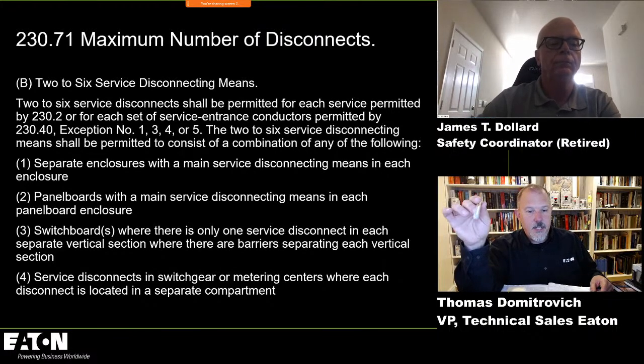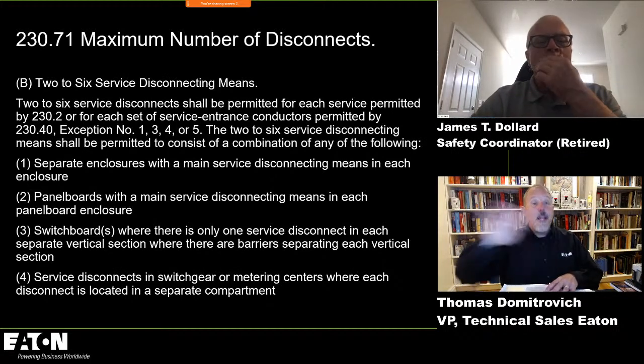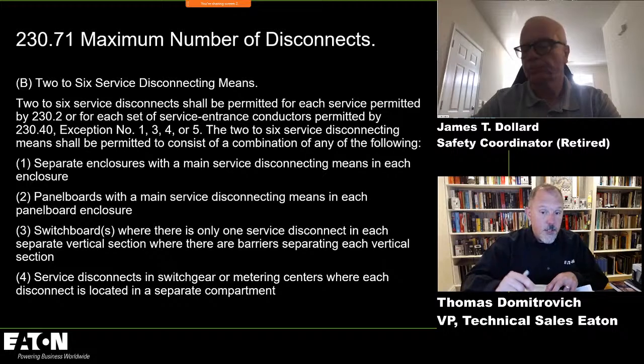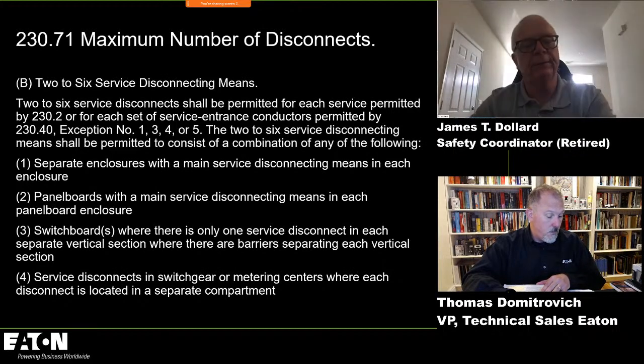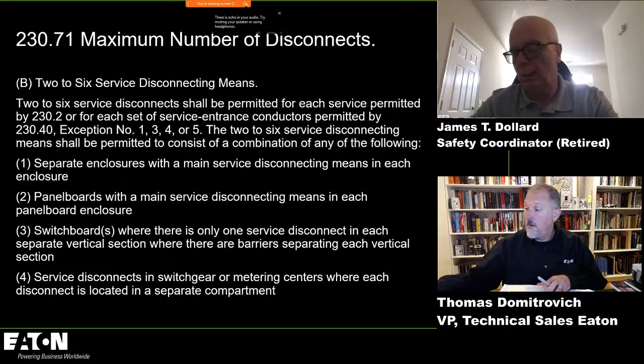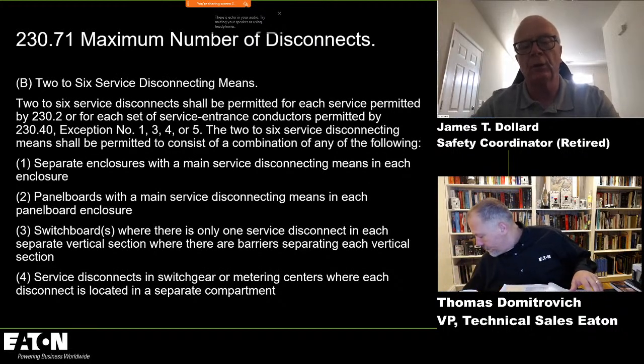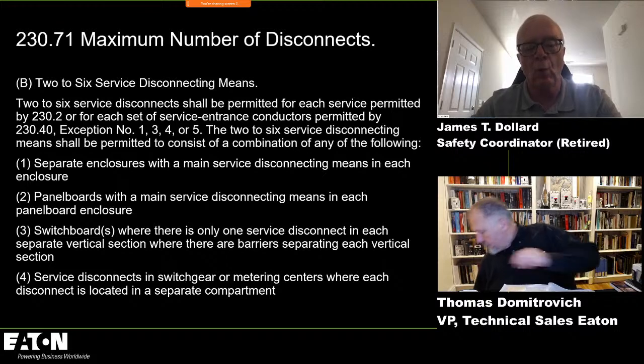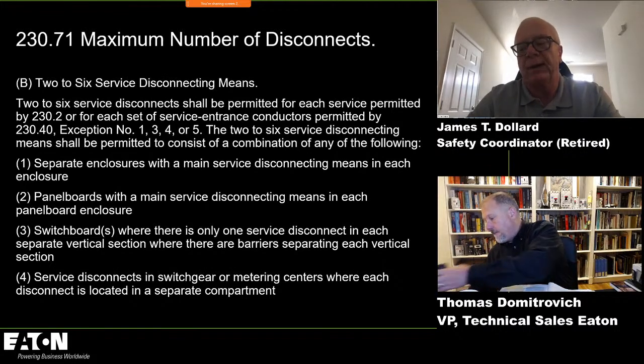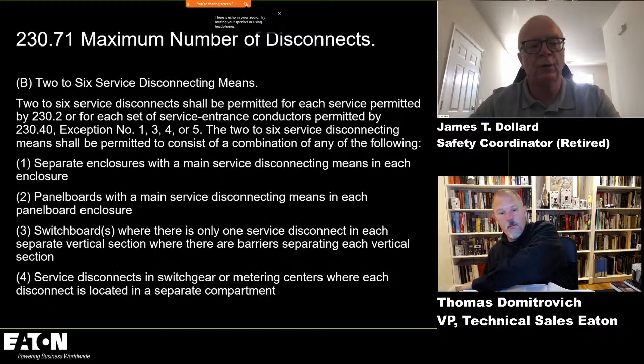230.71B says 2 to 6 service disconnecting means, and they gave us options. We didn't say you can't do it, but we said if you are going to do up to 6 disconnecting means, you've got 4 options to do that. Yeah, and I'm on this committee, and I knew that all we needed was list item 1. Separate enclosures with the main service disconnecting means in each enclosure, because when you get down into list item 4, you're in switchgear. Switchgear is compartmentalized, so you could have 6 in a section of switchgear.